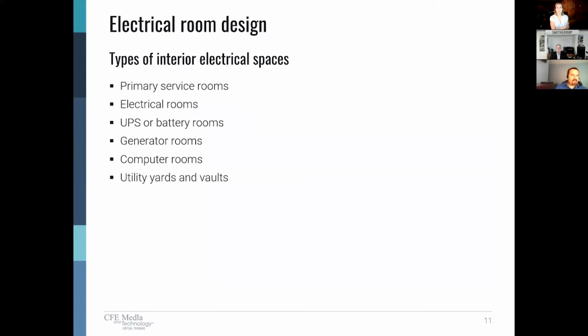So let's talk about the different types of interior electrical spaces that we might encounter during our design within a building. So of course we have our primary service electrical room where we bring our utility feeds into the building. We'll have electrical rooms scattered throughout the building, if it's a multi-floor building, on each floor, serving various areas. And we might also encounter a UPS or battery room where we've got a centralized UPS serving potentially IT loads or the like. And then if we've got NEC emergency, optional standby or legally required systems, or a hospital essential system, we may have interior generators as well, computer rooms, and utility vaults where we may have utility transformers or distribution transformers and primary switching equipment.